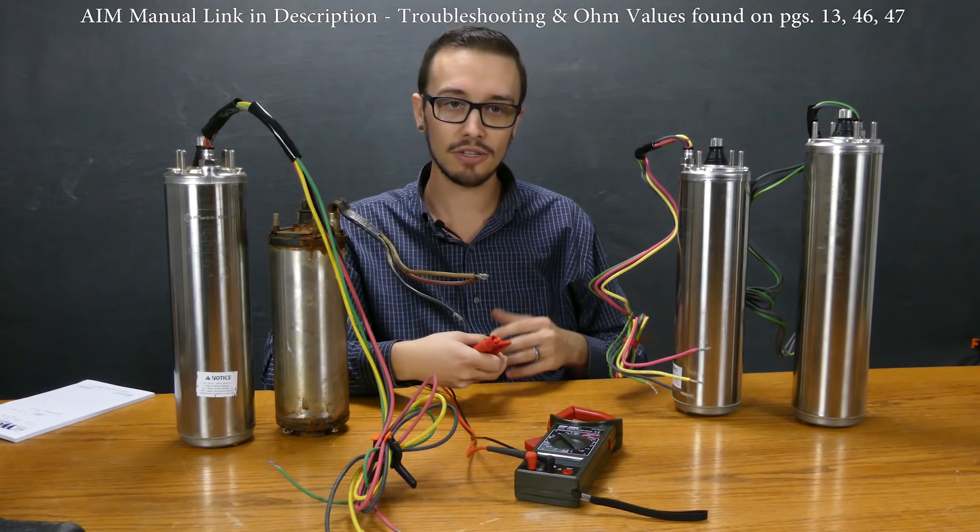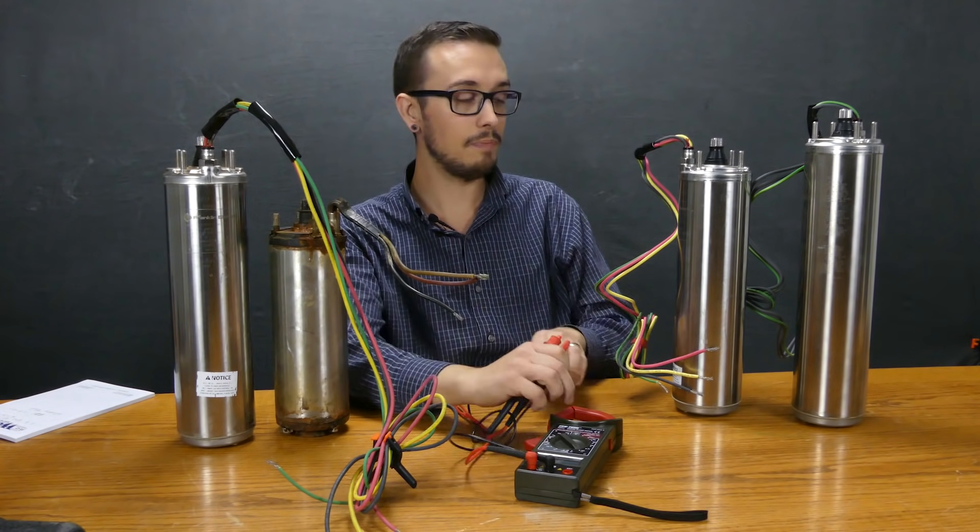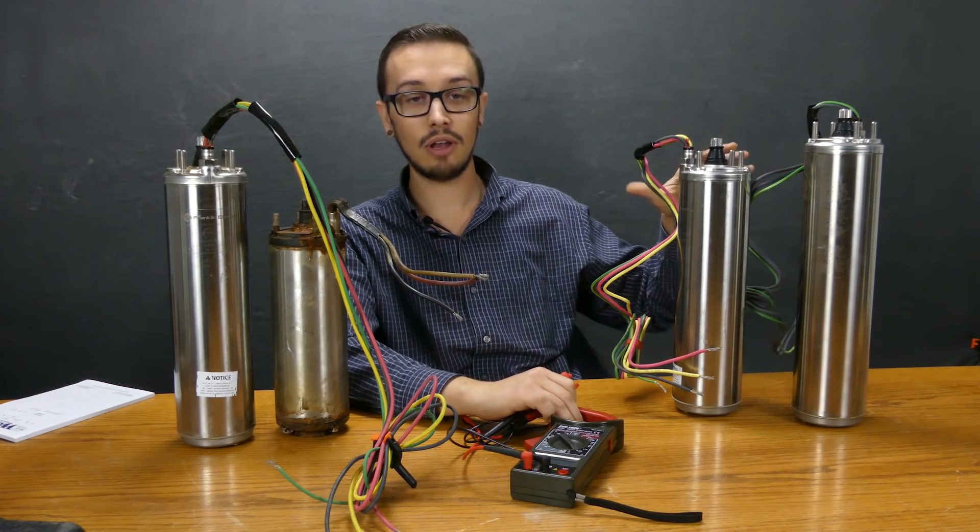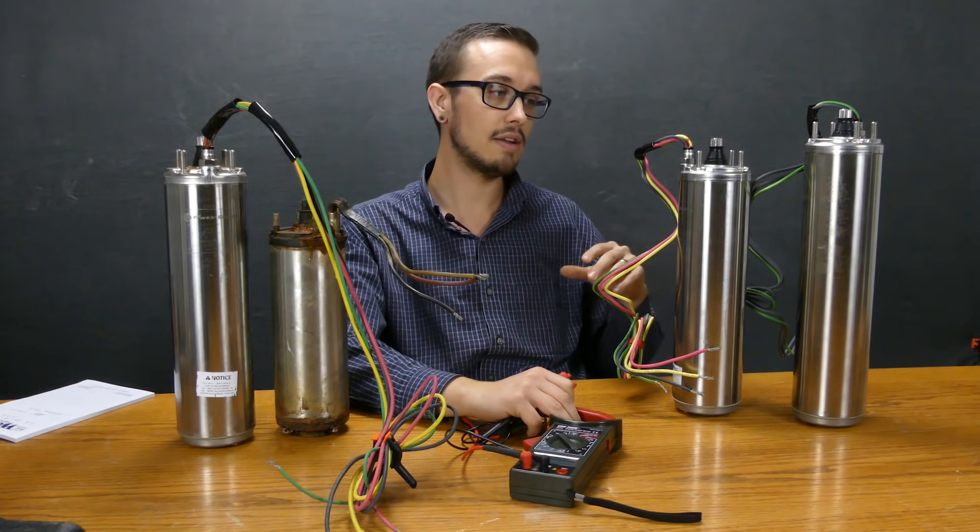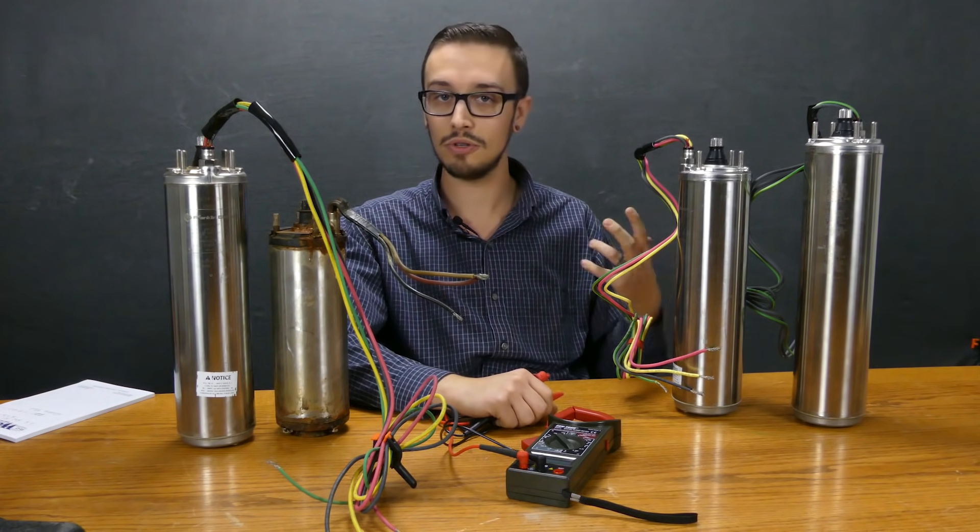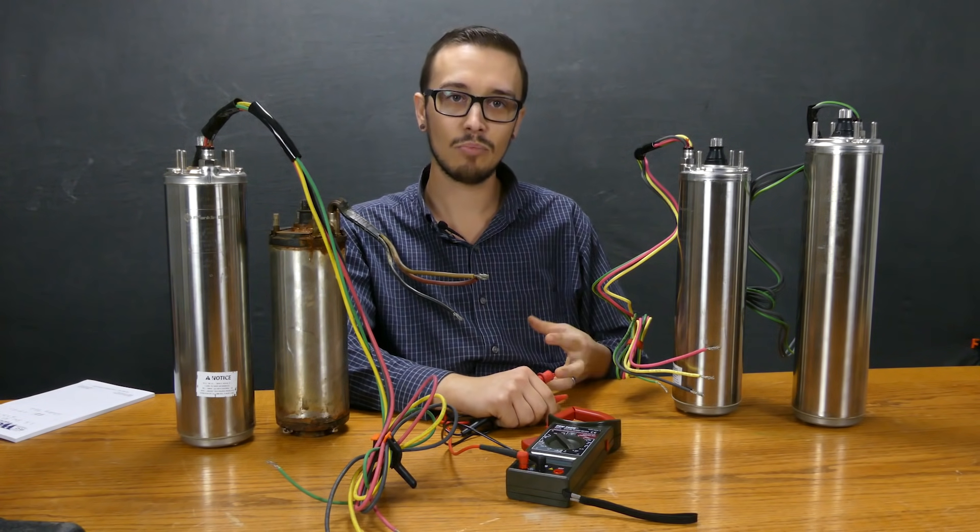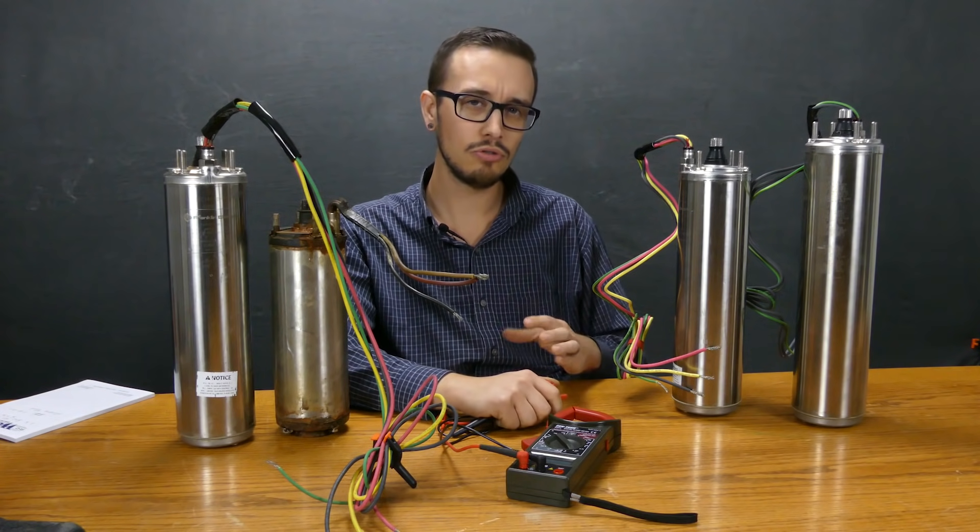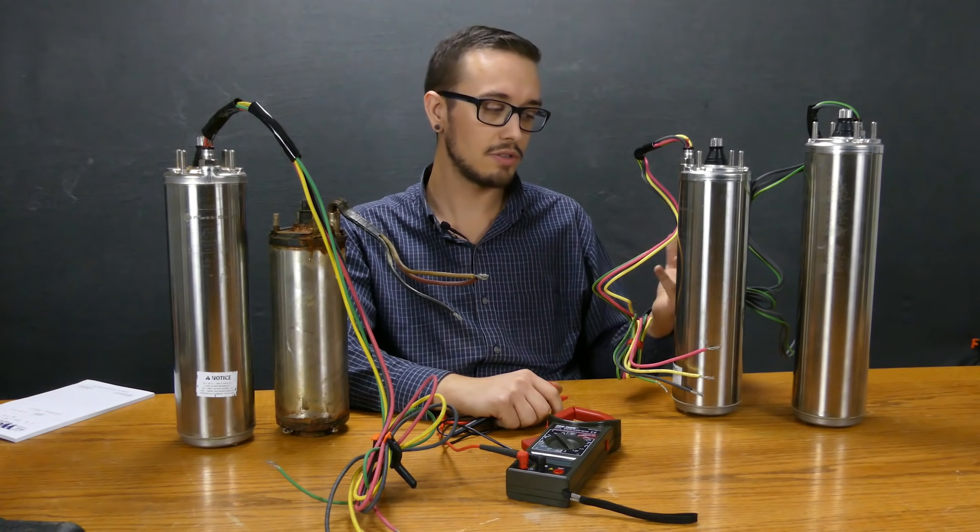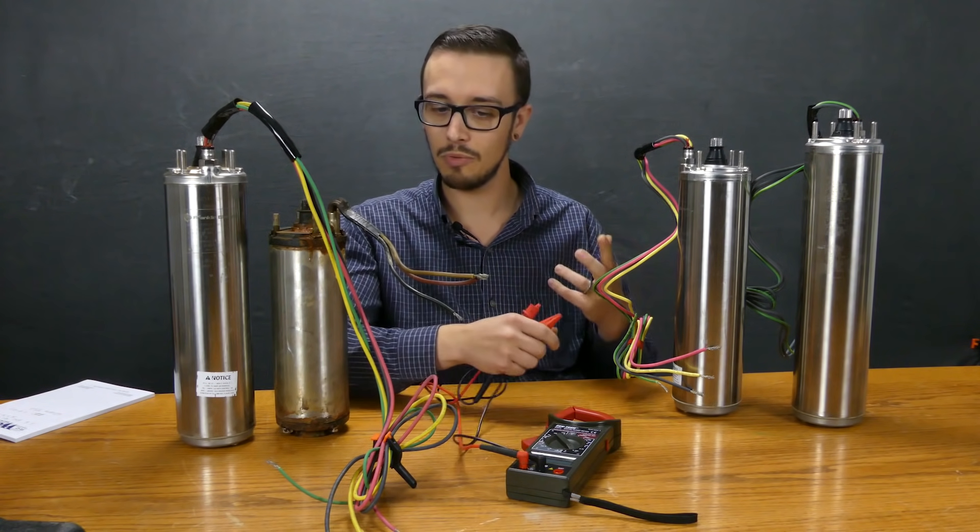These are testing perfectly good on both tests and that's really the only tests that a person can perform on these motors to determine whether or not they're bad outside of high amperage or something like that. But usually these tests are going to ring through on whether or not you've got a problem when it really boils down to it.